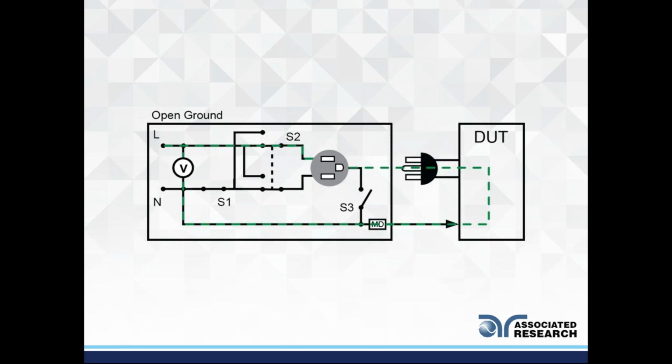So going on a lot of client visits, I notice a lot of people don't run the test with the ground closed condition because logically you're just going to get close to 0 amps, 0 microamps, 0 milliamps. Now when ground is open, that fault current has nowhere else to go but to your DUT, which will now make its way back through the MD where we can make proper measurements of what that current is.